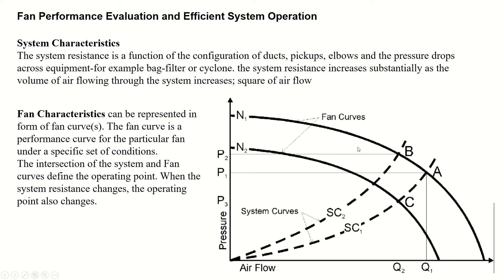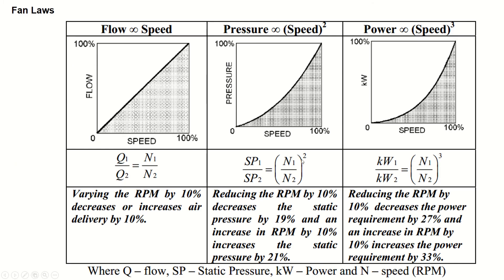We can find operating points using these fan curves and system curves. This diagram also shows the fan laws. The first law states that flow is directly proportional to speed — as RPM increases, air delivery increases in a linear relationship.